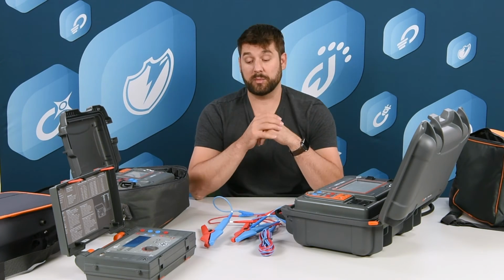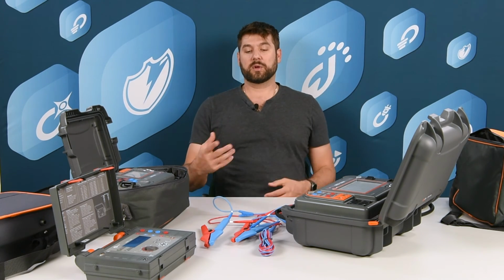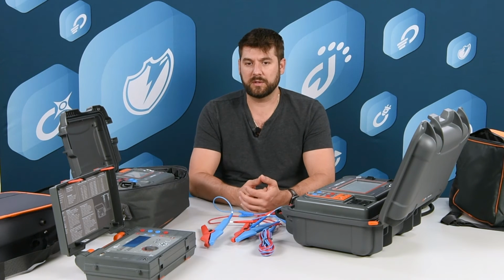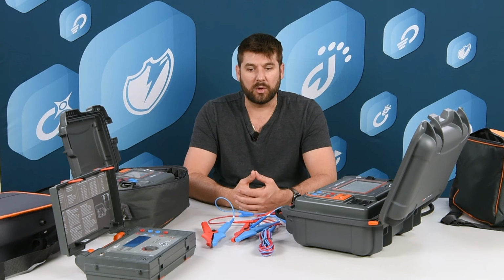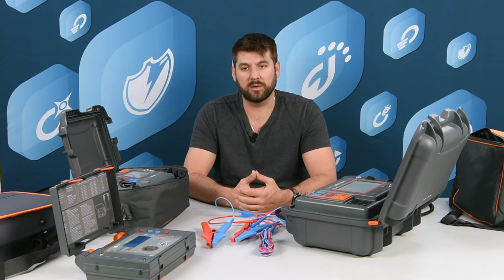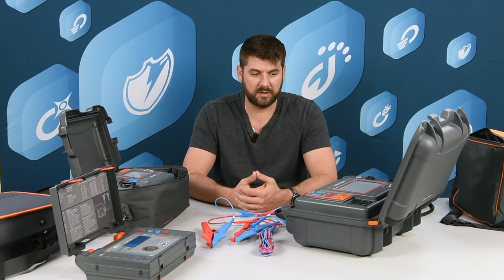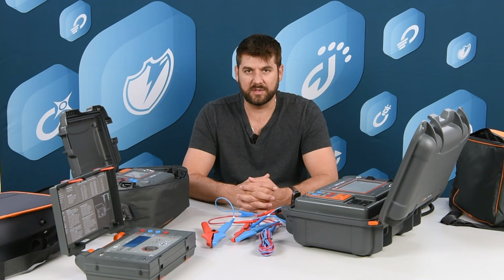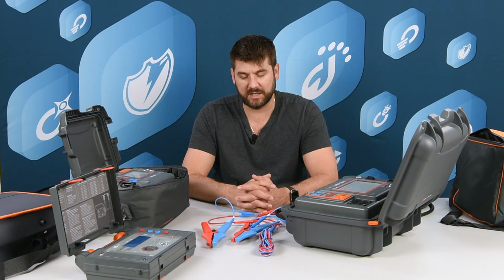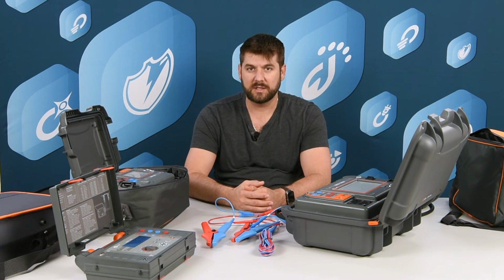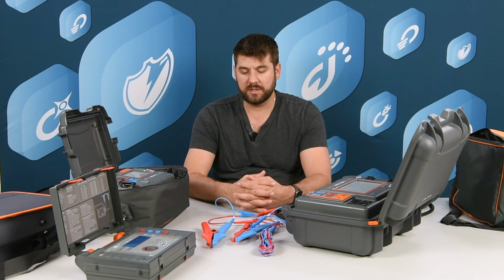We'll get into some of those details later, but basically if you're pushing DC through something for a while, the field inside of a coil is going to continue to add and build up and polarize. It's called polarization. And the longer you push the DC through it, the more polarization you get, and the longer it's going to take to depolarize on its own. So these instruments not only discharge the static, but they can also demagnetize so that you don't have this polarization effect. Because if you push DC through a winding for a long time, say 5 or 10 minutes, it's going to take quite a while for it to discharge.